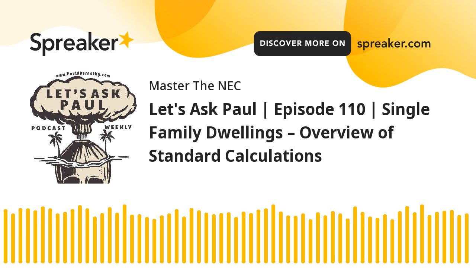So if you got 2 floors, a 3-floor home, every floor counts. And so it's 3 VA per square foot. So for your general lighting and general use type receptacle loads, 220.14J, that's where you're going to do the 3 VA times the square footage using the outside dimensions. So that's where you're going to get that 3 VA per square foot from.